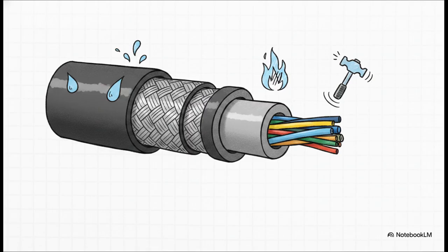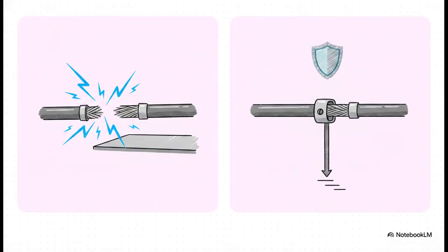That metallic armor actually does heavy double duty. It gives you vital physical protection against impacts, and, as we're going to see next, it acts as a mandatory electrical grounding path. This brings us to why that metallic armor is absolutely crucial. Think about the difference between poorly earthed armor and proper equipotential bonding. First, consider poorly earthed or floating armor. In a hazardous area, floating metal can build up a static charge or create a potential difference compared to the surrounding structures. It's essentially a static ignition risk just waiting to discharge a spark into a flammable atmosphere.